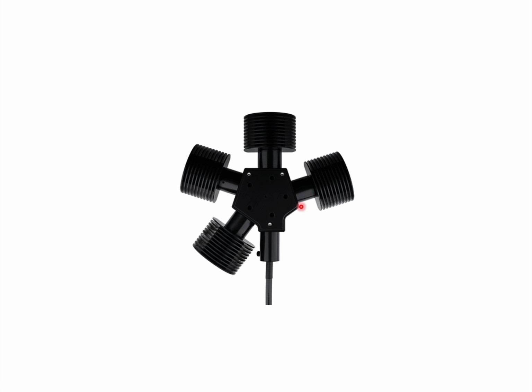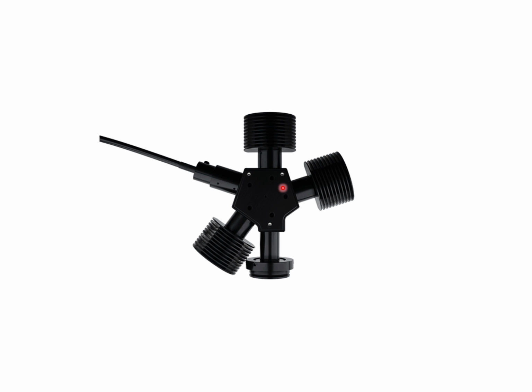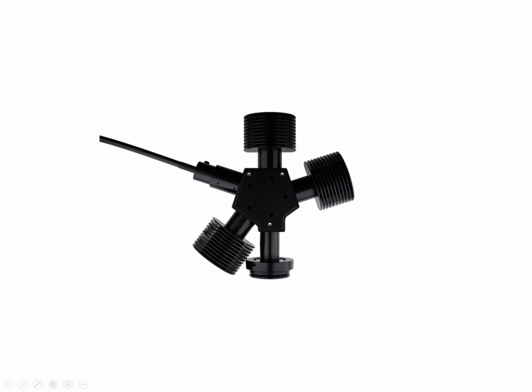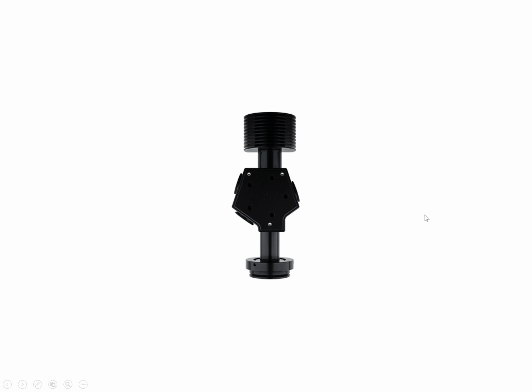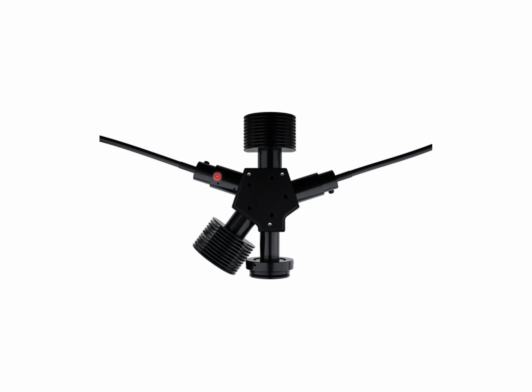So if we just isolated the OBC, the beam combining part, and dropped the controller, for example, you could potentially utilize that OBC to combine any four light sources. One of the easier ways to do that would be through liquid light guides, just combining collimated liquid light guides and attaching those to the beam combining pentagon, as we call it, due to the 5-port configuration. So that would be one of the easiest ways, although you could couple other light sources onto the pentagon beam combining cube directly with the appropriate adapters, which we likely have for you.